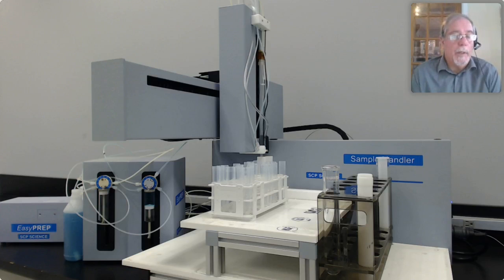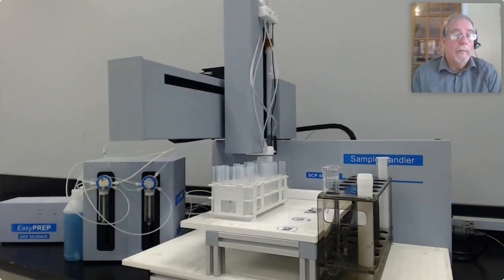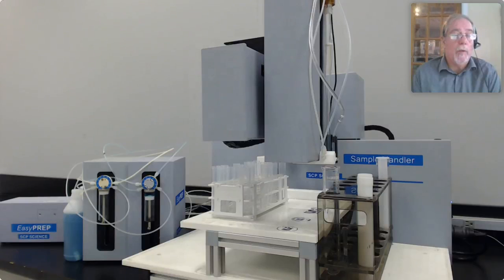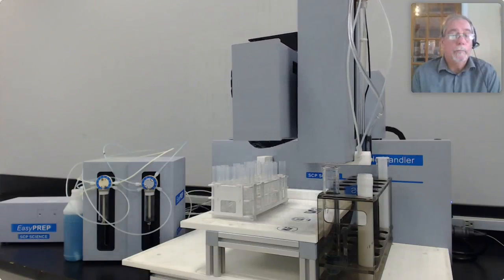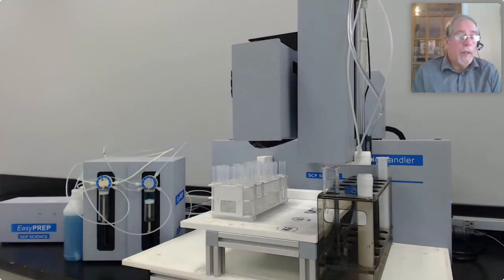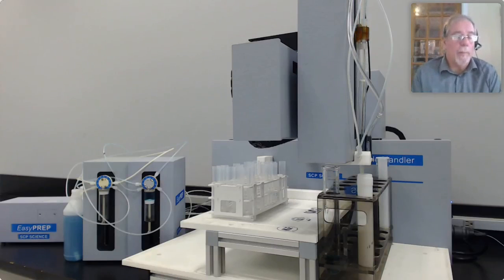So we're priming because we moved from one diluent to another. You can see the blue liquid in the syringe. So now we're going to pick up the aliquot of the acid that needs to be dispensed, which was 10 mils. So we're coming to the tube. We're going to pick up the 10 mils of just nitric acid and dispense it into the tube. So we're going to dispense 10 mils into the first tube. Then we're going to dispense 10 mils into the second tube. And if there's anybody out there doing hydrofluoric acid, we do make an all Teflon pump for doing hydrofluoric acid. So there's our dispensing into the tubes.